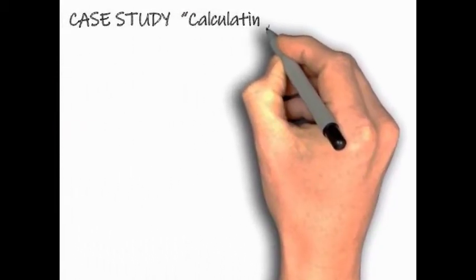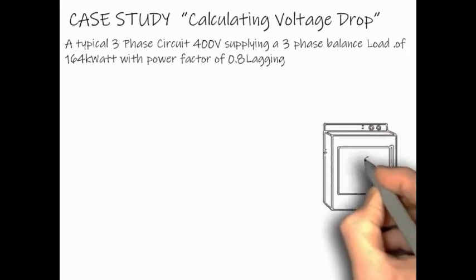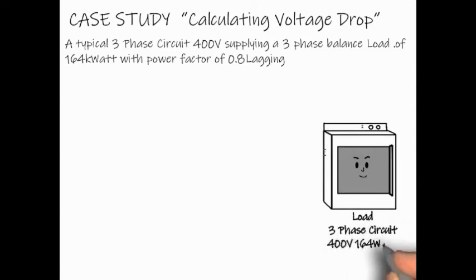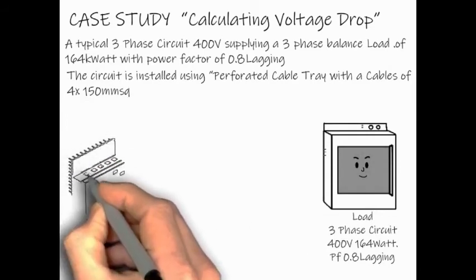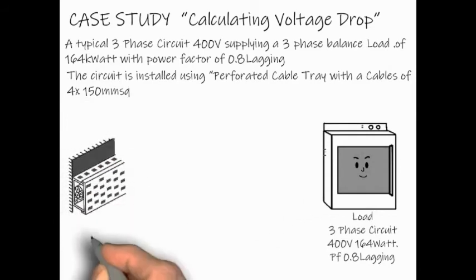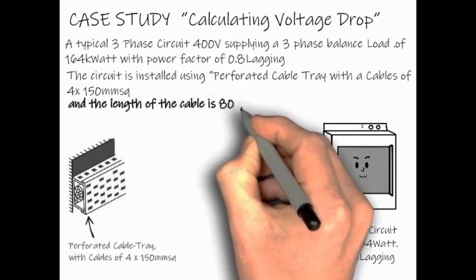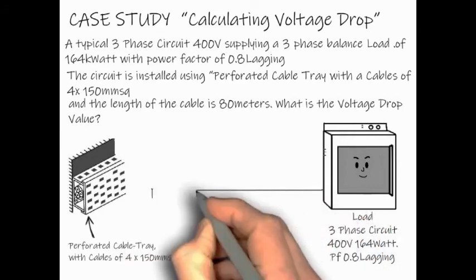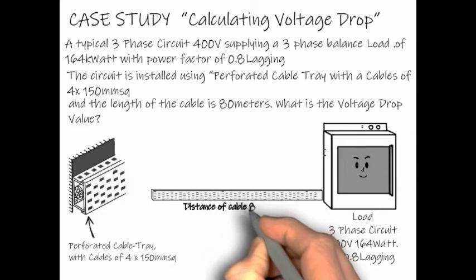Next, we're going to do a case study on calculating the voltage drop using an illustration of a typical three-phase circuit. For 400 volts, supplying a three-phase balanced load of 164 kilowatts with a power factor of 0.8 lagging. The circuit is installed using a perforated cable tray with a cable of 4 by 150 mm squared. The length of the cable is 80 meters. So the question is, what is the voltage drop value?